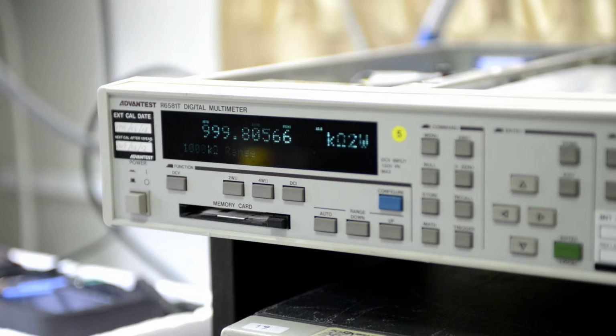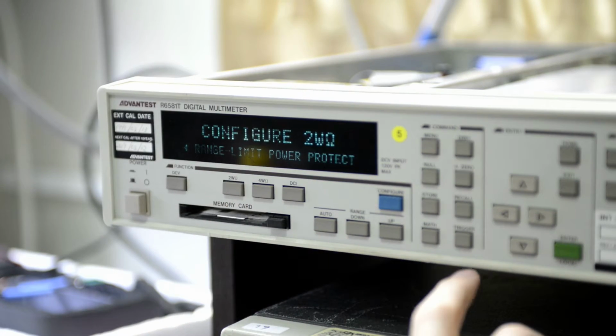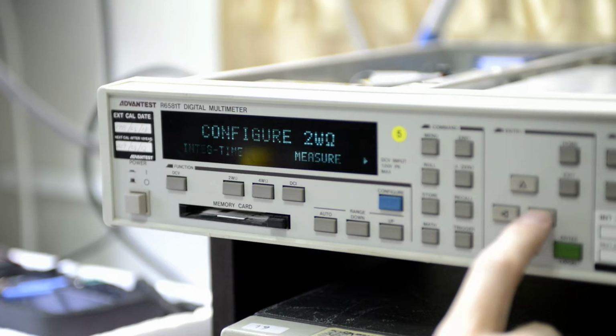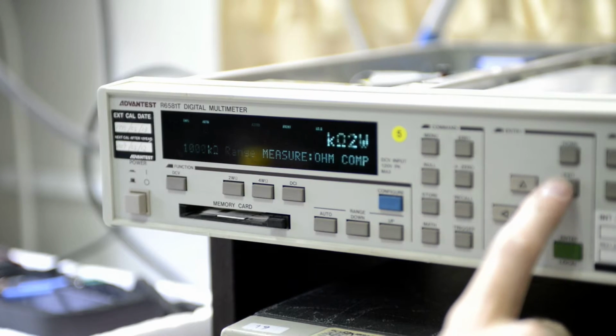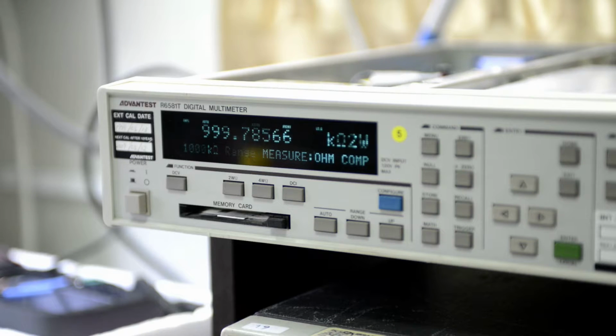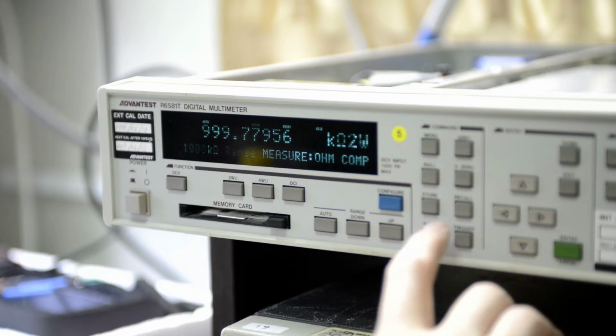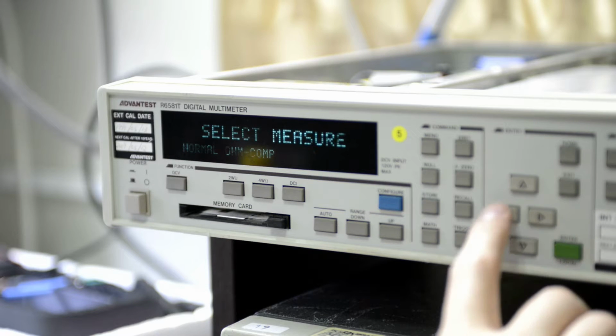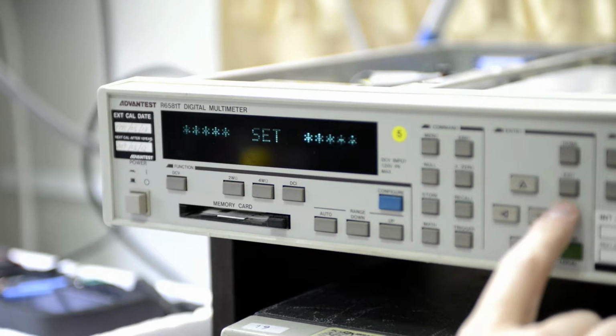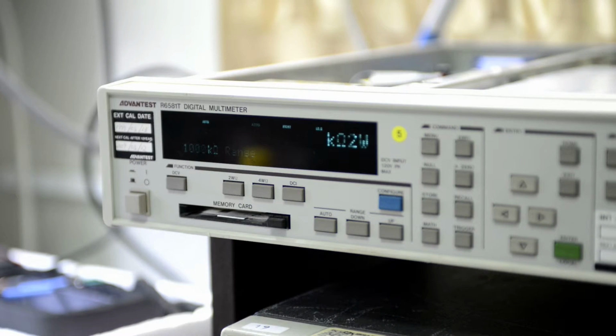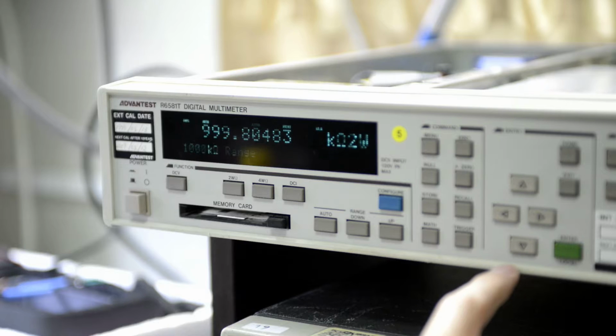So we have about the same value. We can try offset compensation, which should not do much on this high range. Now it's set. And the reading is even worse. It's actually become lower than its normal measurement mode. So we will disable that. And we can go 10 megohm. Range up.